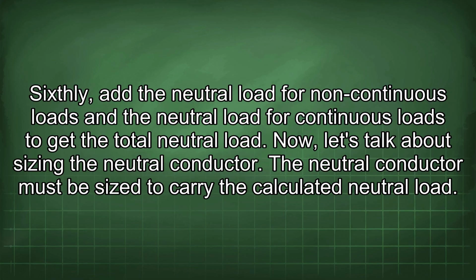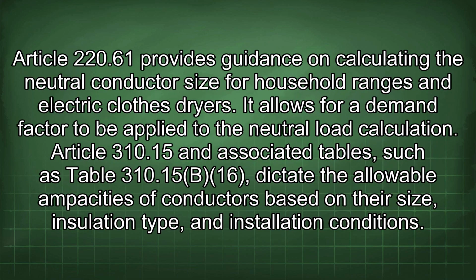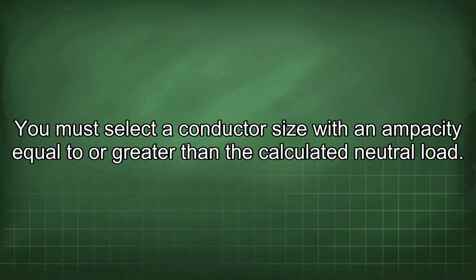Now let's talk about sizing the neutral conductor. The neutral conductor must be sized to carry the calculated neutral load. Article 220.61 provides guidance on calculating the neutral conductor size for household ranges and electric clothes dryers. It allows for a demand factor to be applied to the neutral load calculation. Article 310.15 and associated tables, such as Table 310.15(B)(16), dictate the allowable ampacities of conductors based on their size, insulation type, and installation conditions. You must select a conductor size with an ampacity equal to or greater than the calculated neutral load.